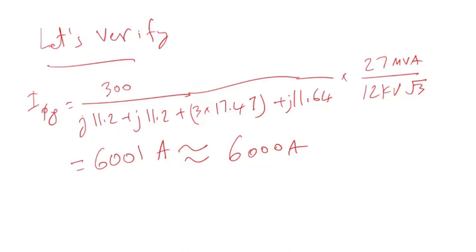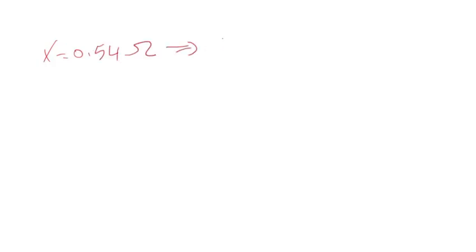Hello and welcome to Engineering Simple. In this video series we learned a couple of things: one, how to calculate the line-to-ground fault imposed on the low voltage side of a transformer. We calculated the fault current in the example to be 11,000 amps, then we wanted to limit the fault current to 6,000 amps. We proceeded with two options — option one, we added a neutral grounding reactor and calculated the reactance of that reactor to be 0.54 ohms.